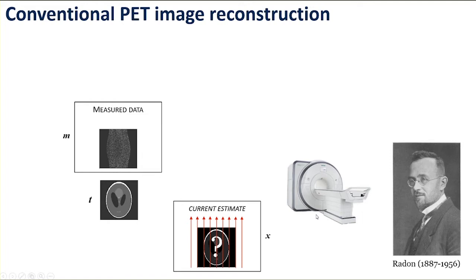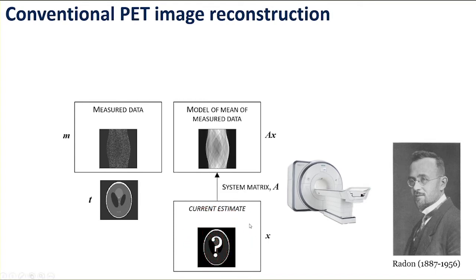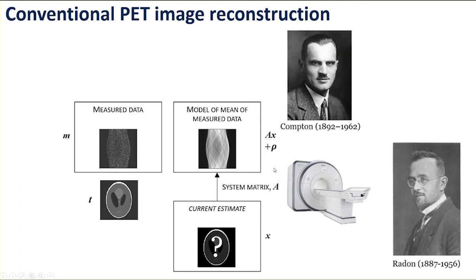This is where we can apply our physics models with conventional PET reconstruction, where we model the scanner with a cascade of linear operators — for example, to model positron range as well as the geometric component, which is often modelled by the Radon transform. I'm denoting that by a collection of line integrals around that radiotracer distribution, which gives rise to a sinogram — a model of the mean data. We forward model using matrix A, the core part being the Radon transform — a forward projection — and then add other models such as Compton scatter.